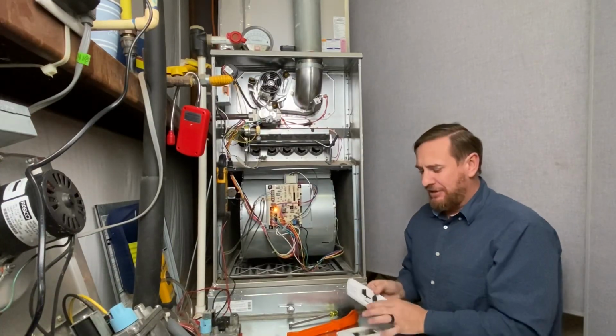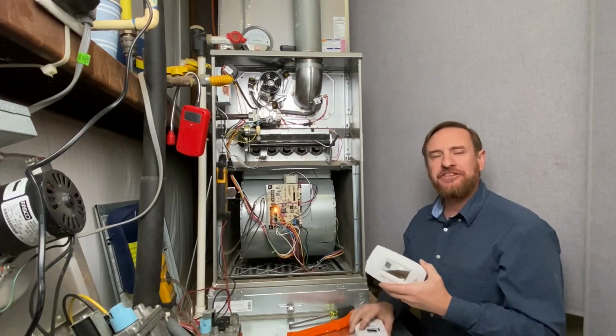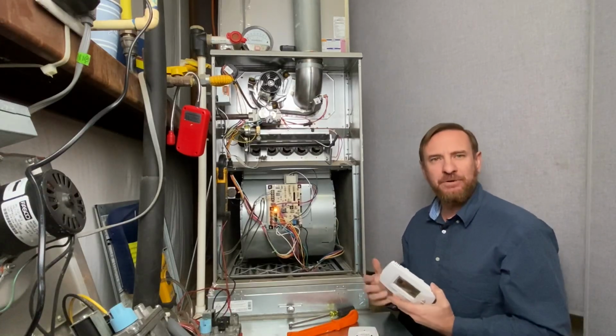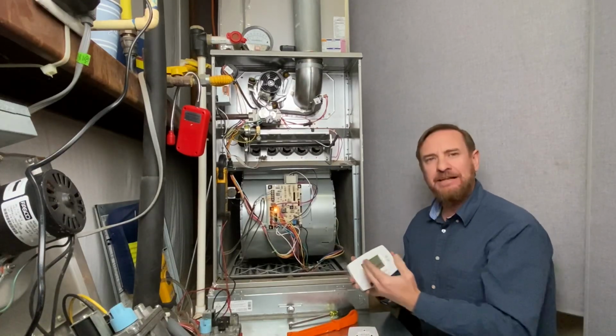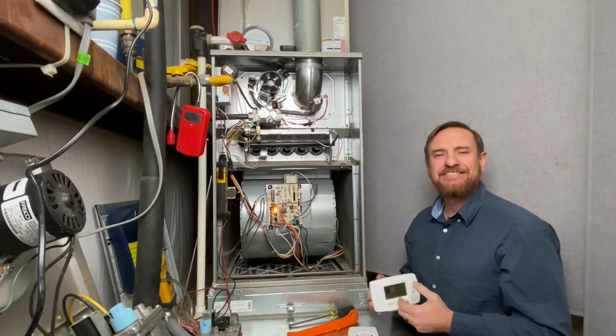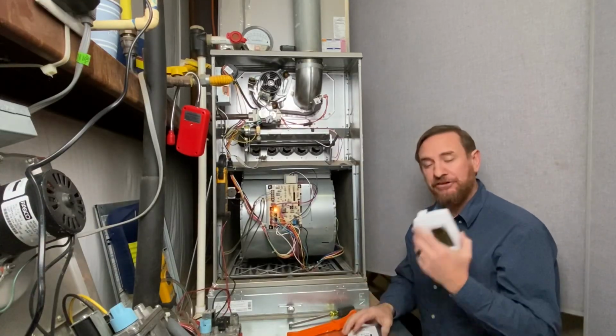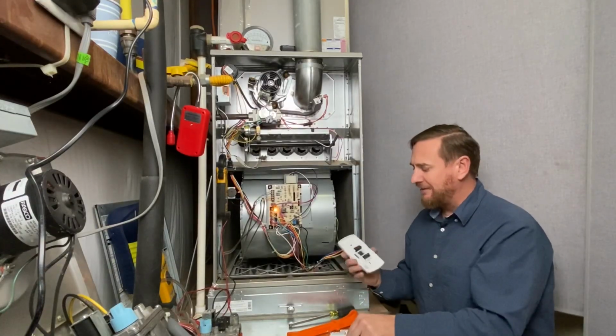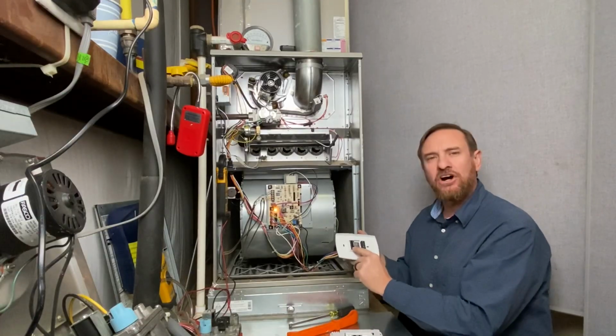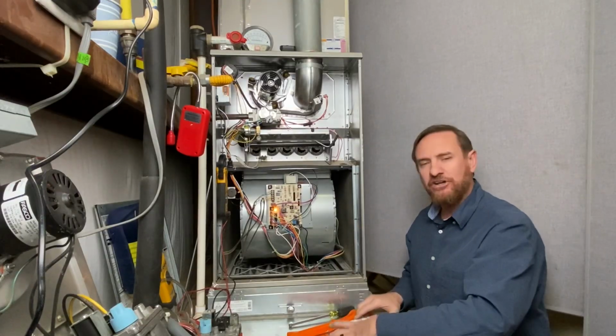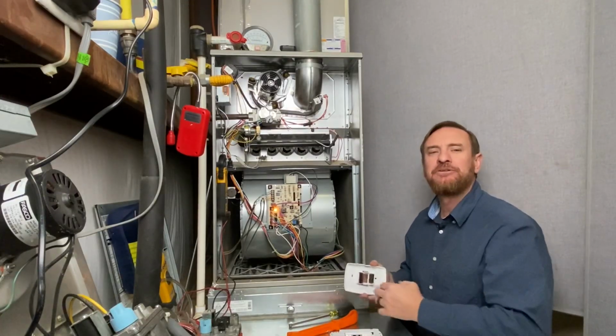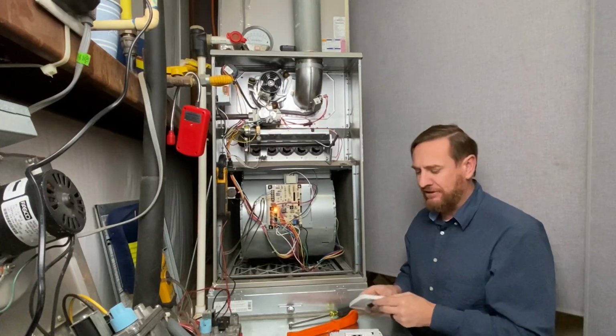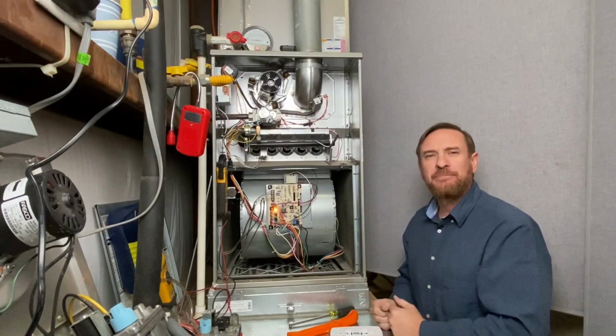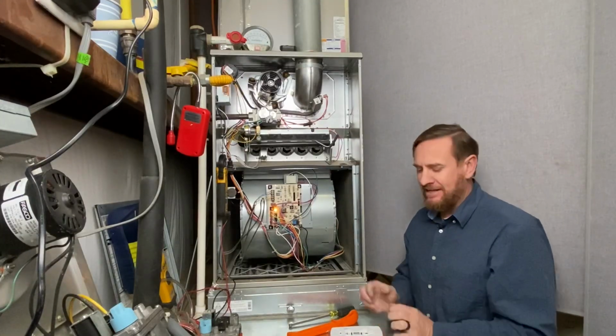Perfect timing. So when we say the thermostat calls and the thermostat satisfies, it's vocabulary words that we use in the field. Calling for heat means it's connected to wires, and satisfies means it's disconnected from wires. Remember, this is just a switch. And on the heating side, we're only concerned about the R and the W terminal. So when it has a call for heat, it connects R and W. When it satisfies, it breaks R and W. So when we say the sequence of operation starts with the thermostat, that's where we start.